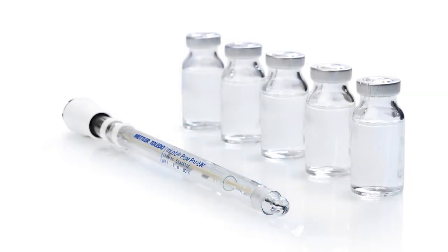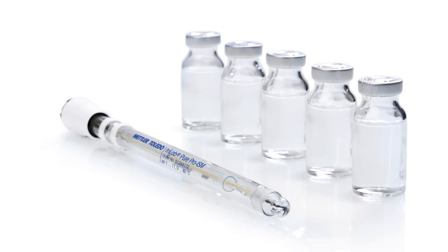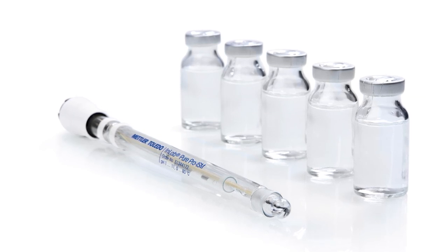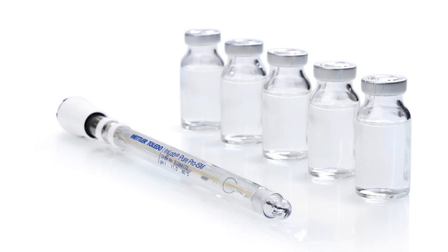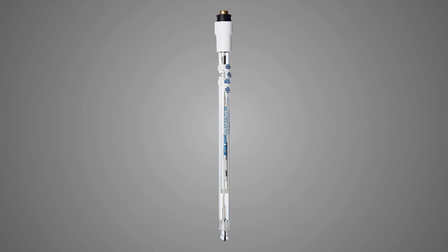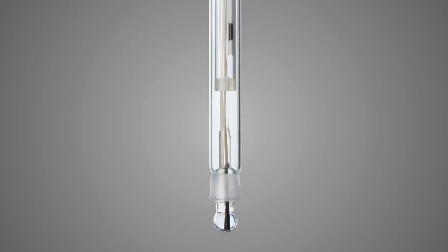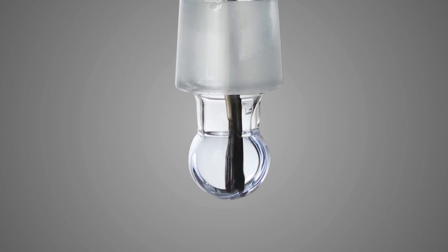Mettler Toledo offers a specialist sensor, InLab Pure Pro ISM, for pH measurement in low ionic and pure water samples. This sensor has a pH-sensitive membrane made of LoT glass, which has a low resistance, and it has a spherical shape to offer a large sample interaction surface. This results in fast response time and measurement of even very small changes in hydrogen ion activity.